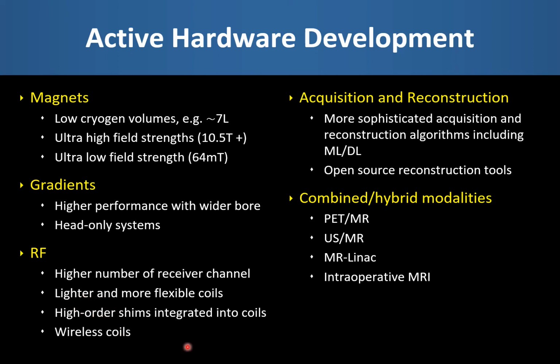Optimization of the static magnetic field, this shimming process we've talked about before, can also be improved by the fact that some groups are looking at integrating higher order shims into the receiver coil elements. So this means that we can really improve field uniformity over quite small fields of view. And then finally, all of the vendors are actively working on developing wireless coils without the bulky cables and connectors that are currently being used.